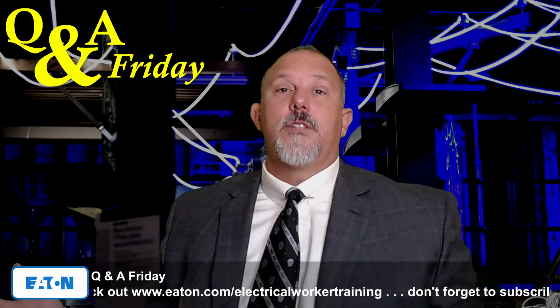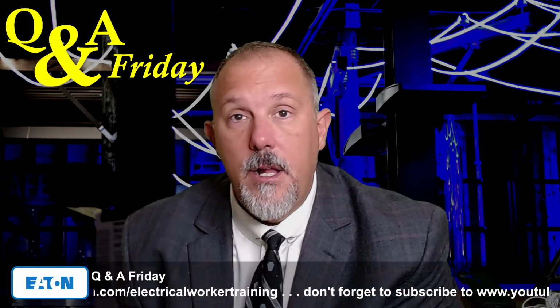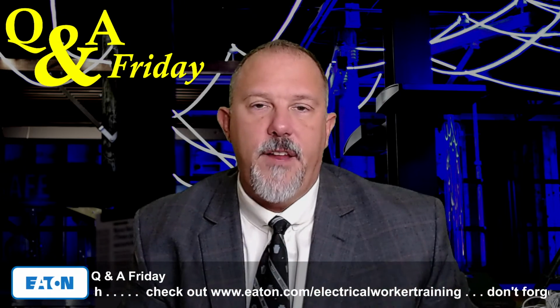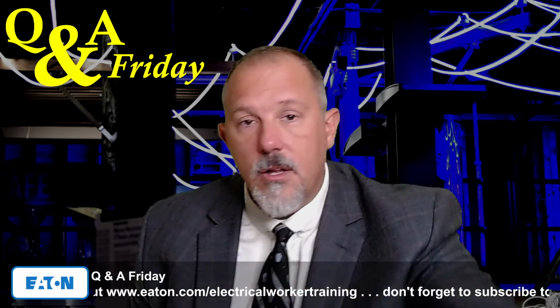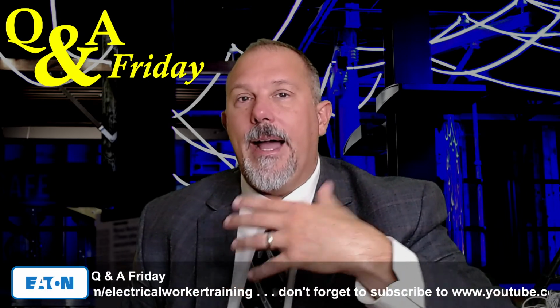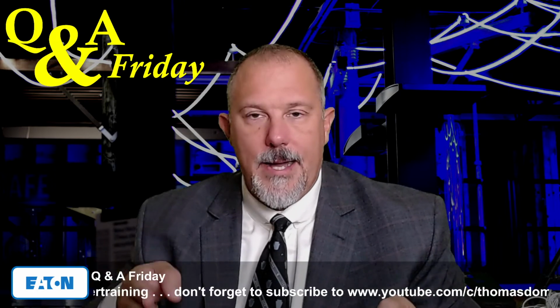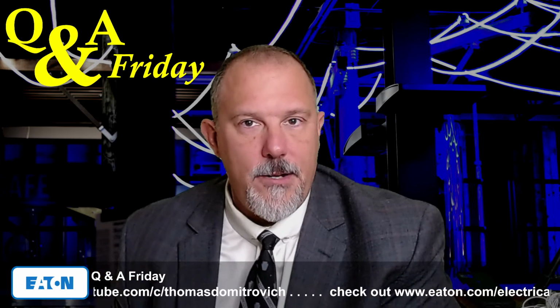What do we use to calculate arcing current? What document, what reference? IEEE 1584. As long as I'm within the limitations of IEEE 1584 with regard to voltage, with regard to available bolted fault current, grounded versus ungrounded, all these different things, you'd have to take a look at 1584 and look at the scope and all that good stuff. As long as I'm within those limits, then I calculate two values of arcing current, a lower and a higher, and then I use both of the clearing times based upon my overcurrent device. I don't compare my three-phase bolted fault current value when I'm calculating incident energy.